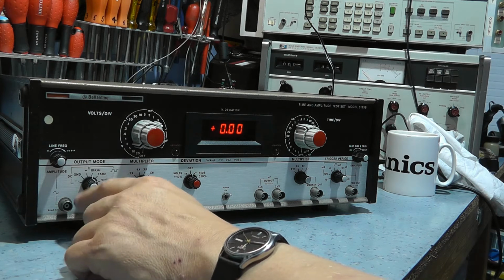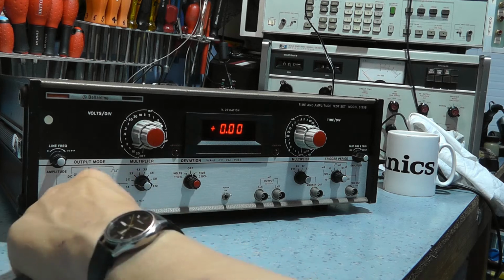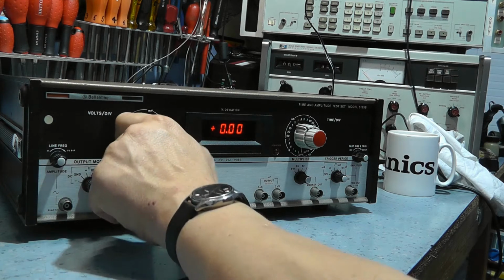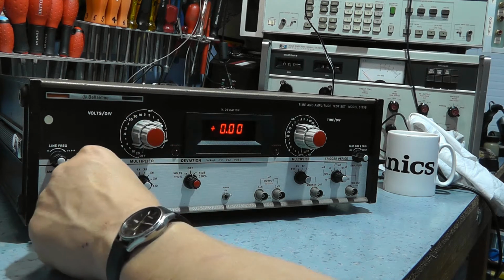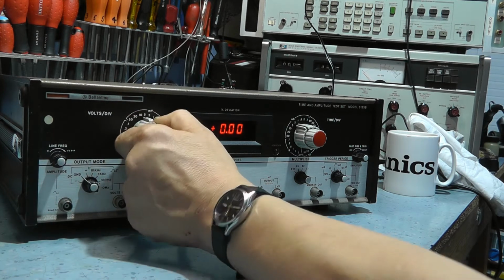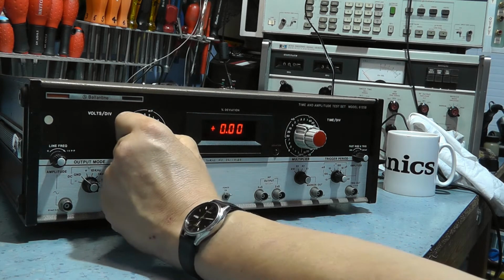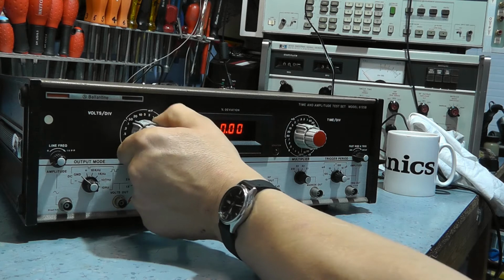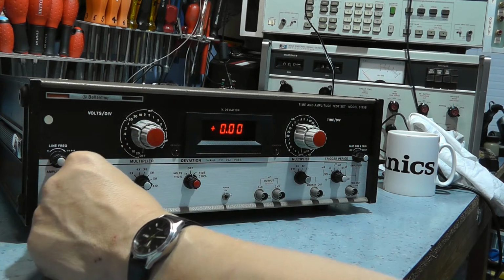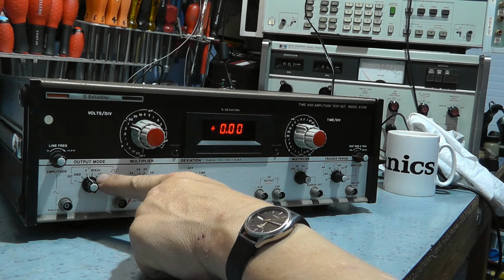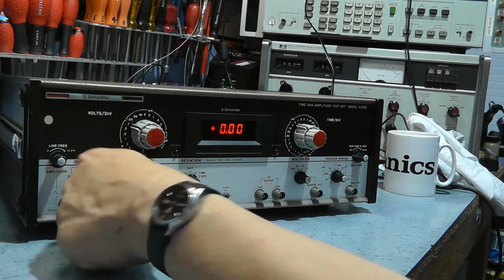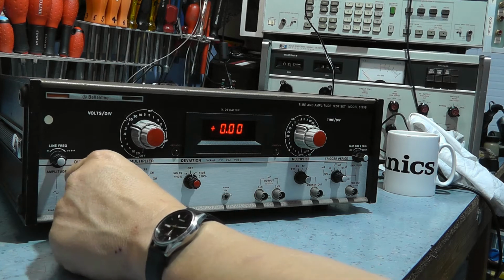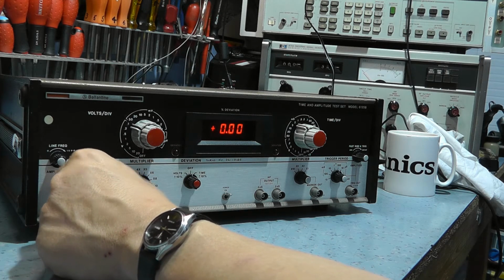You've got an output mode switch here, and basically what this does is whatever range you've selected, it will output. So if I set this range switch here, for example, let's set that to 0.1 of a volt, on DC - that will give me 0.1 of a volt DC. In ground, obviously there's no output, and on minus, it's obviously minus 0.1 of a volt DC.